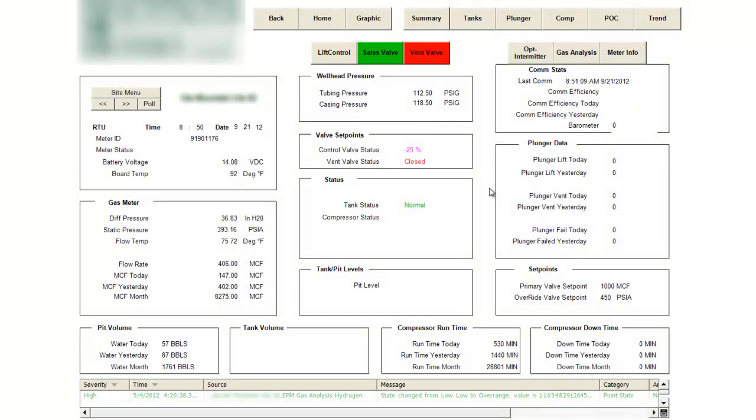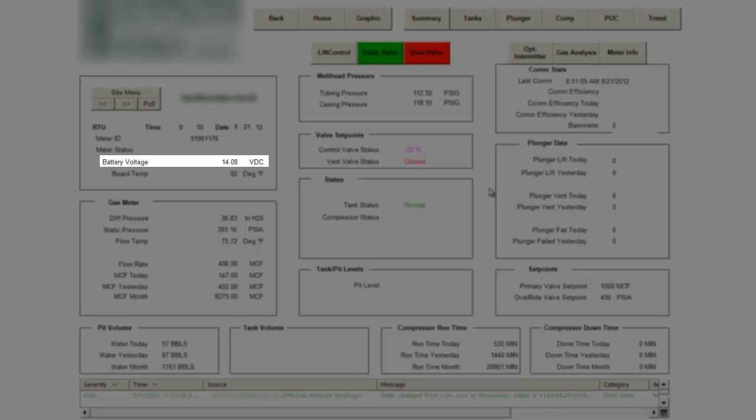One other piece of data that can play into comms troubleshooting is the battery voltage. Often if battery voltage goes too low, communications will be cut off, and it can be difficult to troubleshoot because it will be intermittent. Often it'll be in the middle of the night because the solar panels are not recharging the batteries at that time, but when the sun comes back up, they start to charge the batteries and communications are restored. This can also happen if there's inclement weather, a lot of cloud cover, and the solar panels are not recharging the batteries. You can get an interruption in comms, and it will restore seemingly for no reason, and it may turn out that the battery voltage has just dropped low enough that it turns off power to the communications equipment. A great way to troubleshoot that is with the same tool we just used, is to look at a historic trend on the battery voltage.